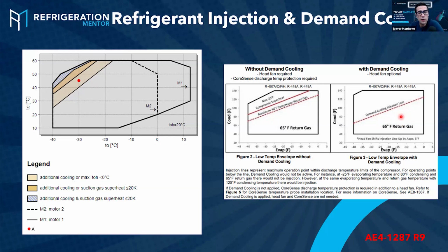So if you have demand cooling, or you don't have that CoreSense on it, for example, you've got to go with demand cooling. Okay. If you're down below here on this operation envelope, below this demand cooling injection line, it wouldn't be injection. But if we're running up here, we would be injecting. So this is in Fahrenheit now. So we'll do 120 Fahrenheit and minus 20. That would be injecting, because we've got to cool that stuff down. Okay. Going back over to this one, if it just has a head cooling fan, you can see it says a maximum of 40 degrees compressor return gas temperature. So if you're in this zone, if you drop it down, you're in this zone, a maximum of 20 degrees Fahrenheit compressor superheat, which is like 9K or something like that, Kelvin.